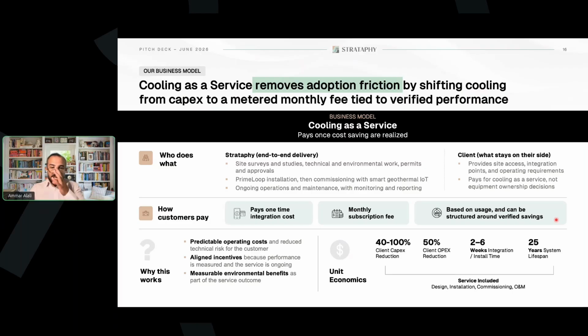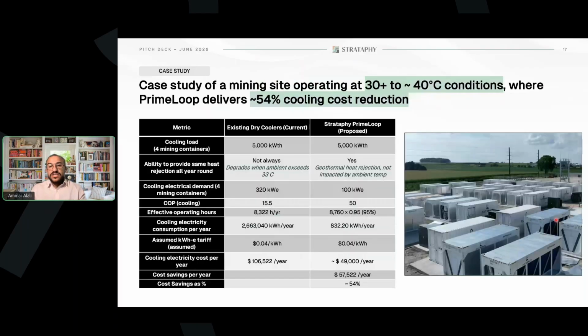Quick case study: we can't say specifically where it is, but it was roughly 5 megawatts, using dry coolers with no compression. Whenever ambient temperature exceeds 33 degrees, dry coolers don't give the same efficiency or performance, resulting in a COP of roughly 15 for that specific site. This site operated 24/7, about 99.99% of the time at the same load, with a tariff of roughly 4 cents per kilowatt—so they were spending roughly $100,000 on cooling costs, mainly electricity.